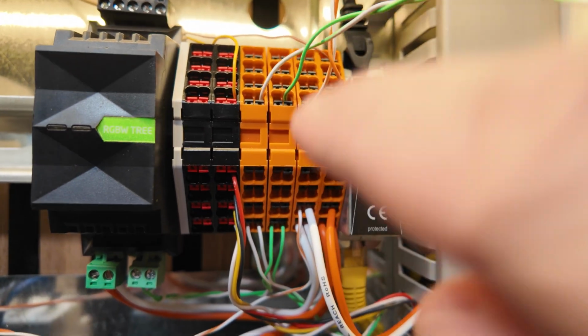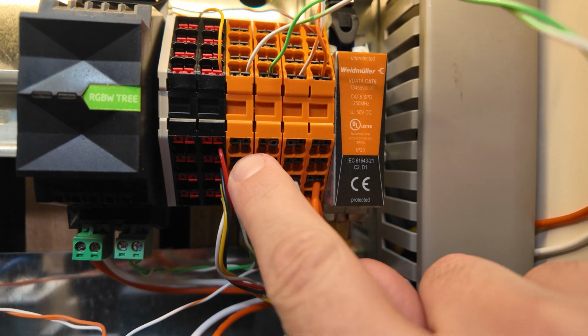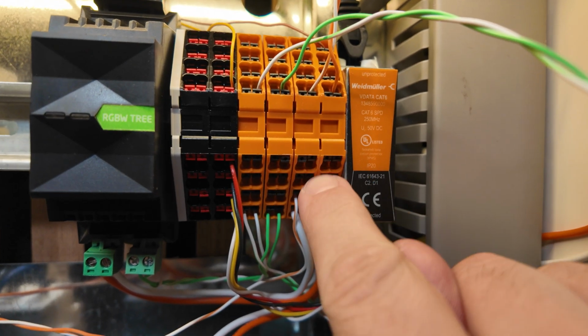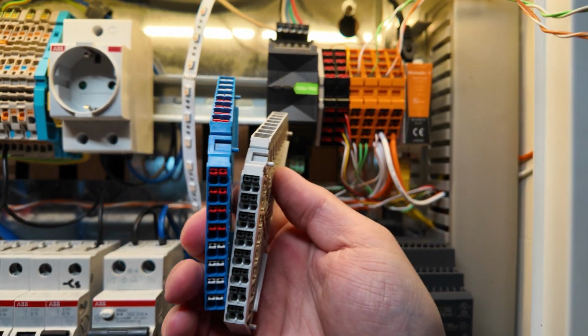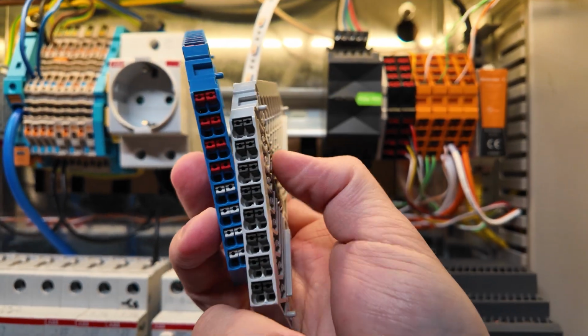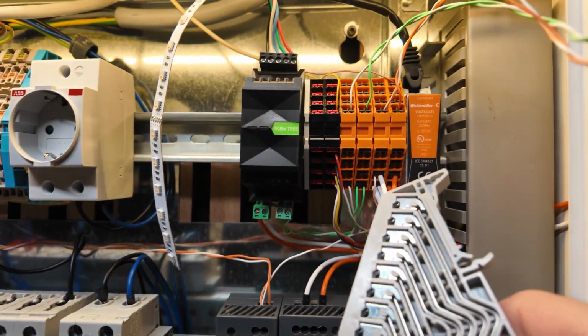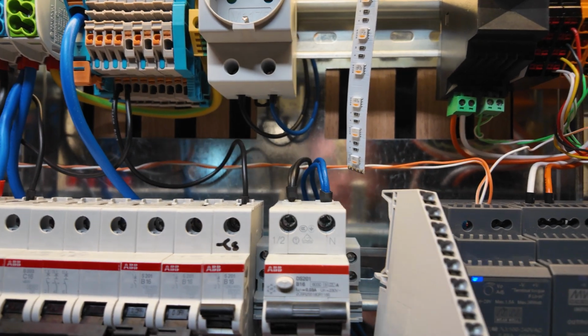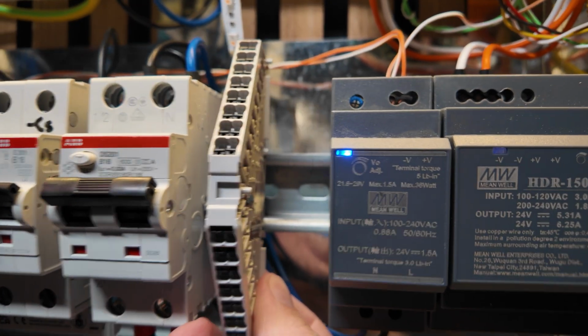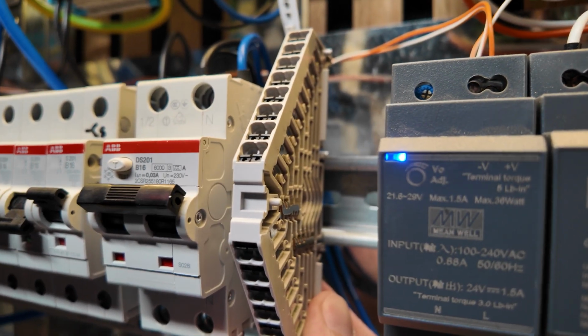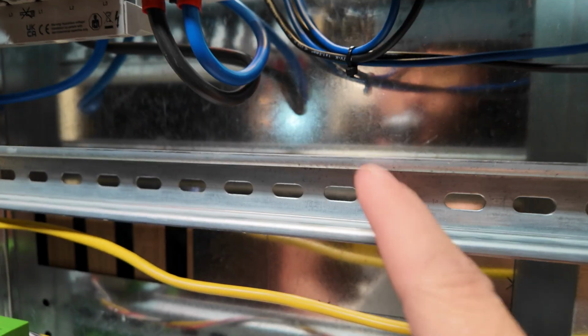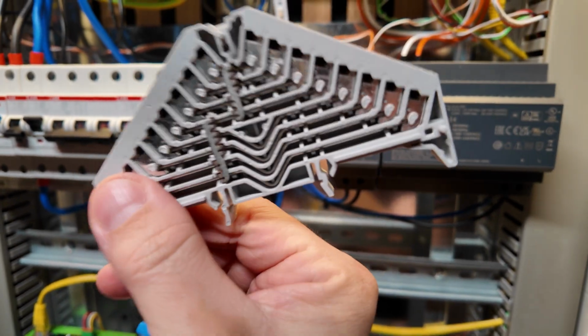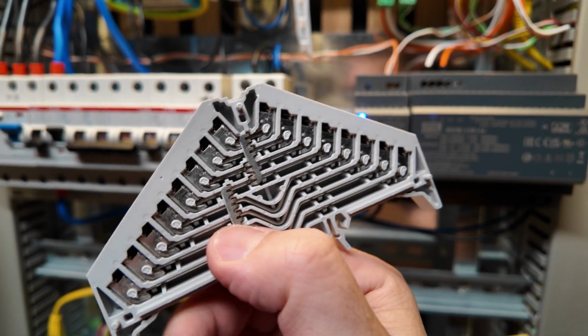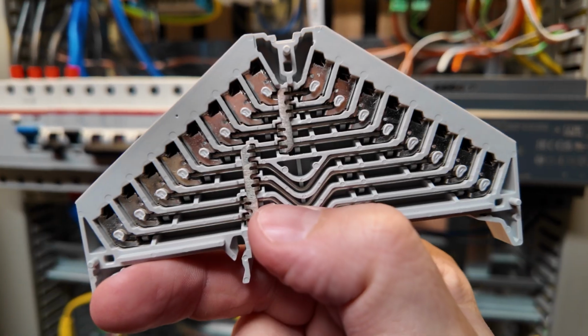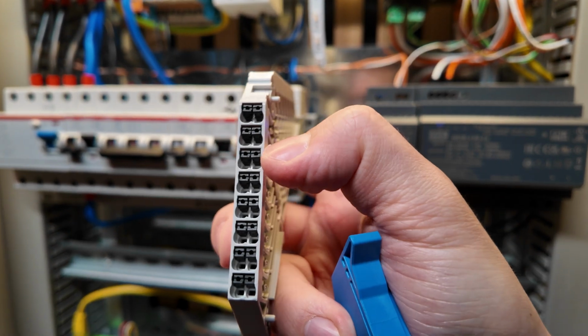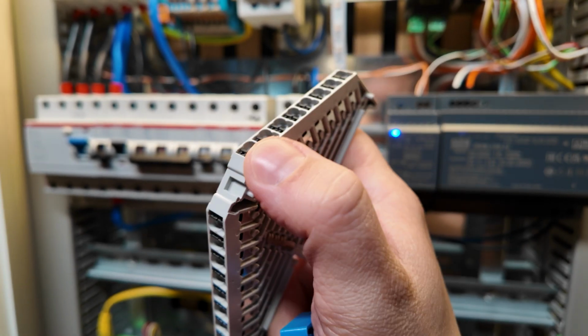I typically put the 24 volt and the tree branches on those Weidmüller terminal blocks. There are different sizes available. Here is an 8-row clamp. This one is a 4-row clamp, but take care, typically those ones do not fit nicely in the normal cabinets if you're not able to mount the DIN rail further back. And as you see, this clamp here is connecting every input on both sides. So whatever you put here, here, here, here is always connected to everything else.